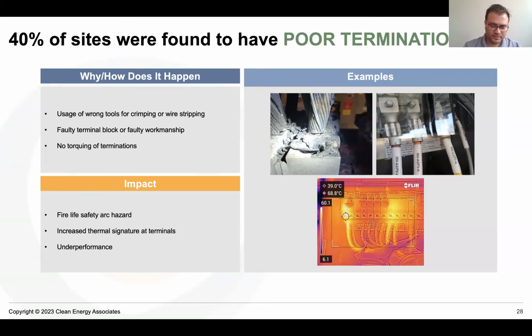Yeah, and not to forget, a lot of times we have seen technicians using the wrong tools for crimping, wrong tools for wire stripping. But even when we point out it's a poor termination, what they do is they take out the cable and they reinsert the cable and they call it good. That's not how it works. When there is a poor termination, the correct way to fix it is take out the cable, cut off the poor termination, restrip the cable with the correct tools, and re-terminate the cable, re-torque it, and put a torque mark. The entire process needs to be repeated.